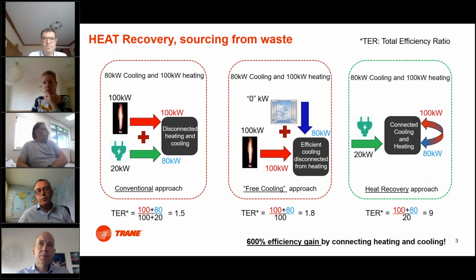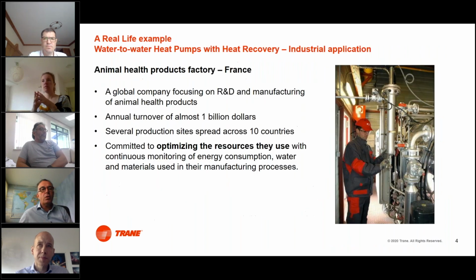It's very normal to have an EER of 4, so a COP of 5, which is the balance between cooling and heating and the energy consumption. And if you use both, then you have the 5 and the 4 together, still with that one power input, which generates a 9 at the end of the day. That gives a real indication of the efficiency increase you can gain if you connect the dots well at the right temperatures in a process system. So that's the theory, and now I want to step into the practical experience.